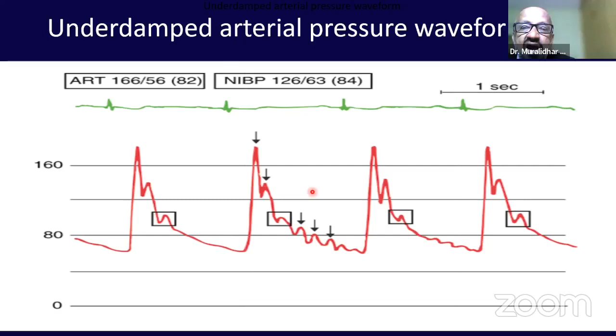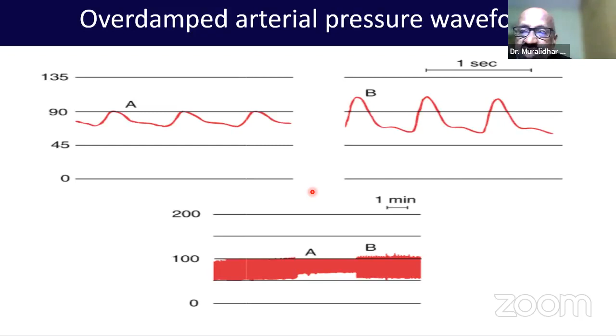So this is the underdamped waveform, and this is the overdamped waveform, where the systolic pressure is lower and diastolic pressure is higher. But again, here the mean arterial pressure is similar to the normal, the actual value. And the usual cause of an overdamped arterial waveform is the presence of clot or air in the system. So you need to remove the clot or the air in the system and keep the arterial line flushed all through to be able to get the actual real-time measurement of the arterial blood pressure.